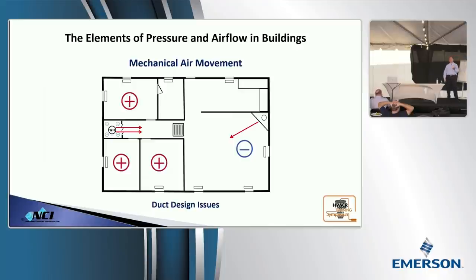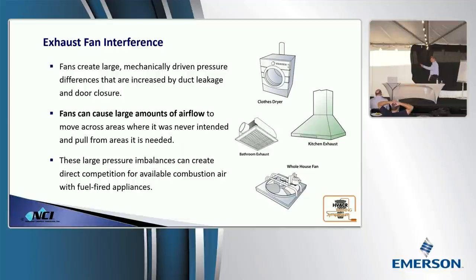So, we mentioned HVAC first because it's one of the biggest air movers. There's other exhaust fans that can create a ton of interference with this. If you put a clothes dryer in here, a kitchen exhaust hood, what are you doing to that effect? You're multiplying it. So we're going to walk through the steps on how to find that. This is where we get into exhaust fan interference.